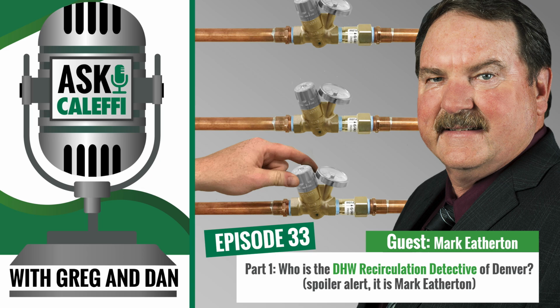So, we go through everything, checking, making sure they have the right temperature coming into it. Is it leaving at the temperature it's supposed to be set to? If you've got a huge building, minimum flow requirements. Are you meeting minimum flow requirements? That's another one that causes a roller coaster ride like that. But a failed check valve, that's another indicator that that's the problem.